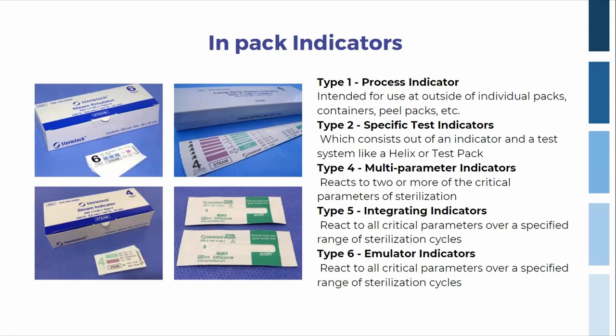Your type 2 is a specific test indicator, which consists of an indicator and a test system like a Helix or Test Pack. So typically that will be your Bowie-Dick indicator. The indicator inside is a type 2, but the challenge is the outside pack. Even your helix, the indicator that you place inside your helix is a type 2, but with the challenge, it's considered a type 2.